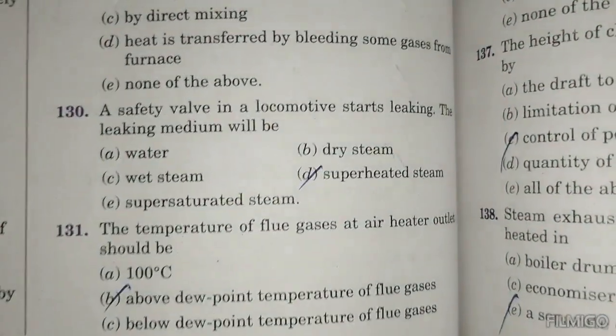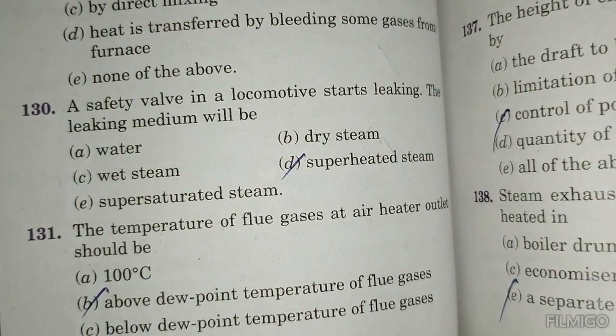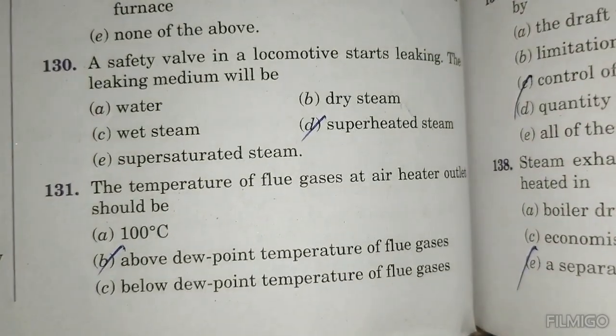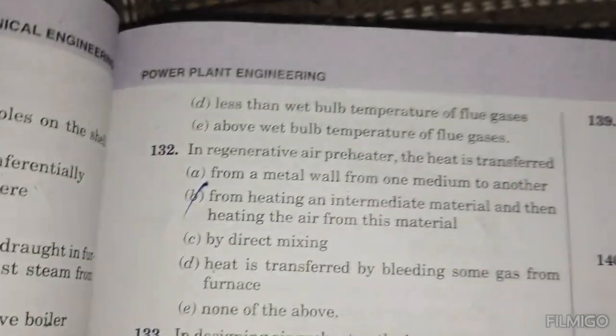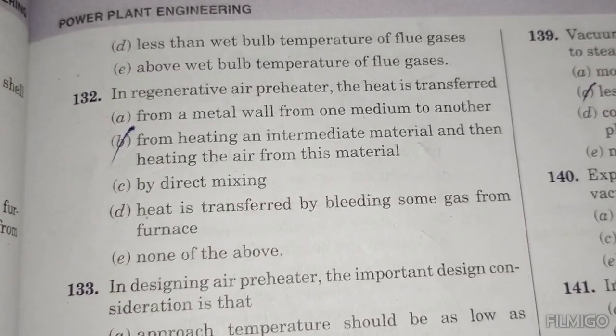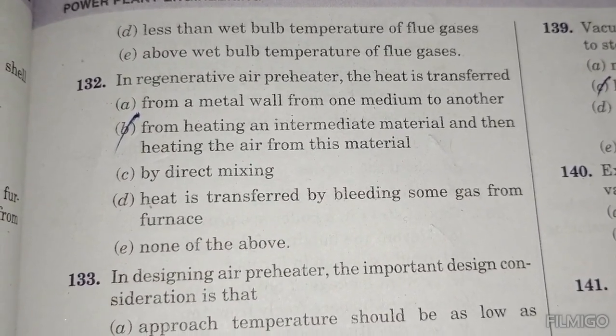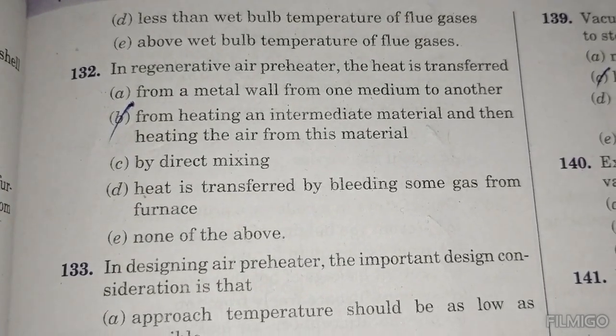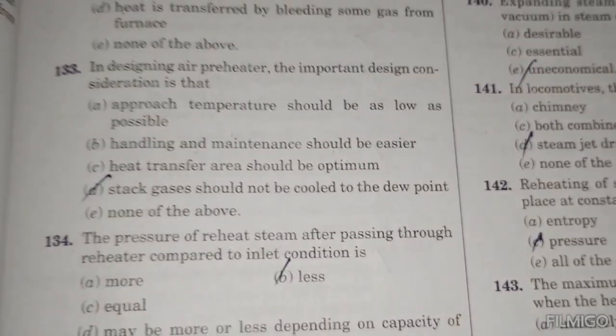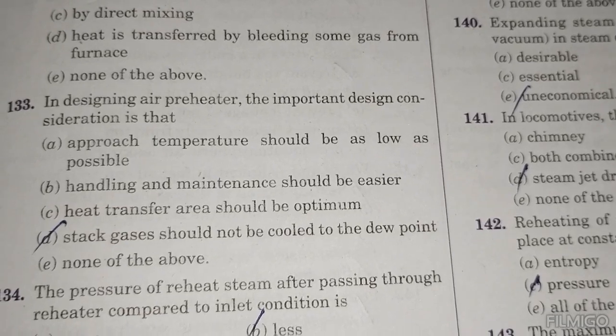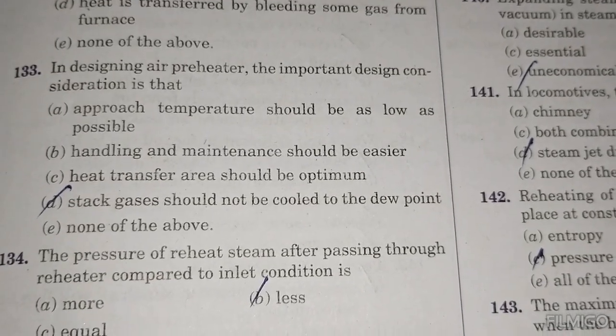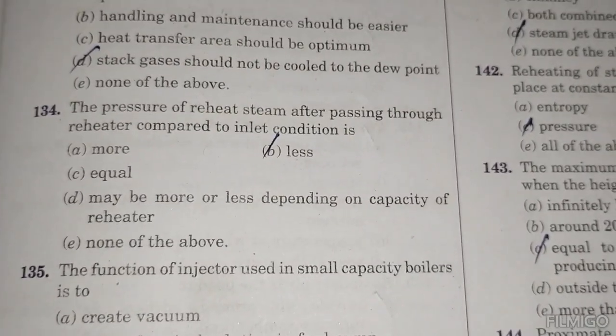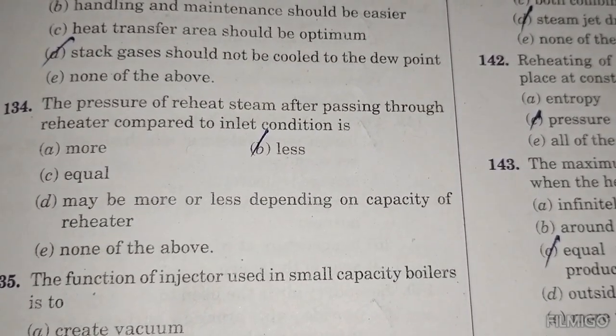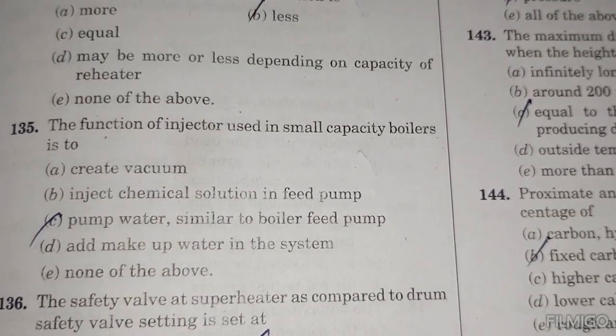The leakage medium will be superheated steam. The temperature of the flue gas at the air heater outlet should be above the dew point temperature of the flue gases. In regenerative air preheaters, the heat is transferred from heating an intermediate material and then heating the air from the material. In designing an air preheater, an important design consideration is that the flue gases should not cool below dew point. The pressure of reheat steam after passing through the reheater, compared to inlet condition, is less.